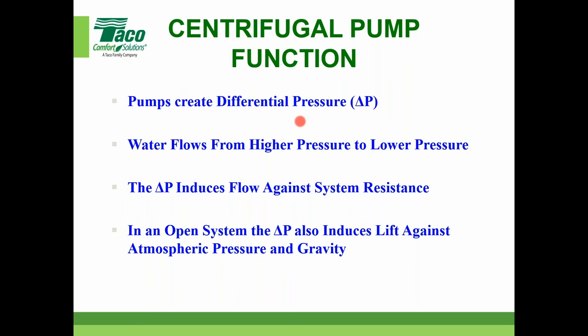The delta P that the pump is creating induces flow against system resistance. Well, that system resistance is calculations that somebody has to do for a hydronic system. There's software out there. We have a presentation in this series that's going to show you that. Actually, last week, Rich showed you how to do manual system resistance calculations, right? But that delta P has to overcome that system resistance. One thing that we like to clarify: most HVAC systems are closed loop, okay? That means they're not open to the atmosphere. In an open system, and more than likely we're talking condenser water with an open cell tower of some sort, the delta P that the pump has to overcome also induces lift against atmospheric pressure and gravity for some little dimension there. So it has to overcome that. In a closed loop system, it does not.